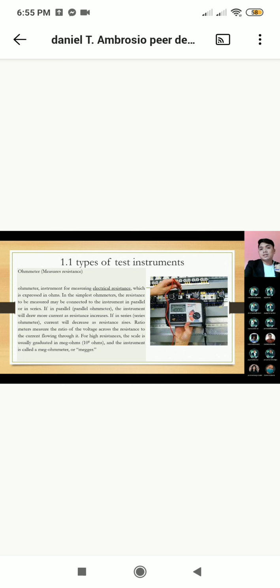Stop, sir. So for the clarification, ohmmeter is used to find the resistance of a certain load. Mostly, the technician calls it a megger tester or insulation tester. This is very useful for a technician, especially if you are a rewinder or an aircon technician, because in outside troubleshooting you can find out if a certain motor is grounded or has weak insulation. And for additional information, a megger tester is usually used by the rewinder. So is it clear, class?